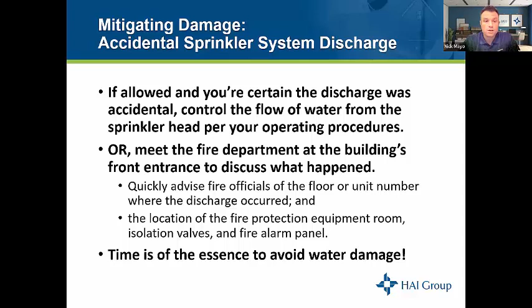Again, if you can provide the fire department information on the location of the fire protection equipment room, isolation valves, and fire alarm panel, it's just going to make their process a little simpler when they're on scene. So time is of the essence to avoid water damage, especially with a sprinkler head. We have tens of gallons flowing from that sprinkler head per minute. So the quicker the fire department can shut down the water supply to that sprinkler system, the quicker we can start controlling where the water is going and where it's going to end up in the actual building itself.